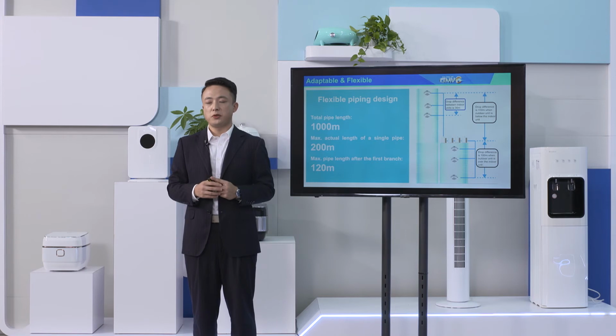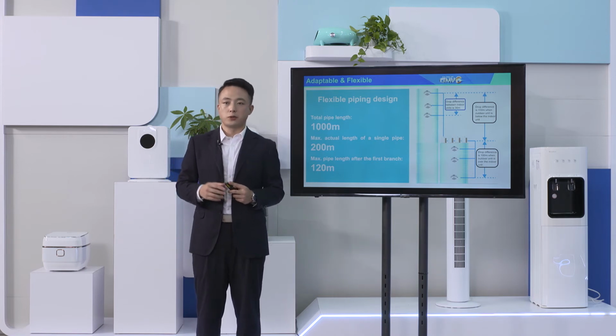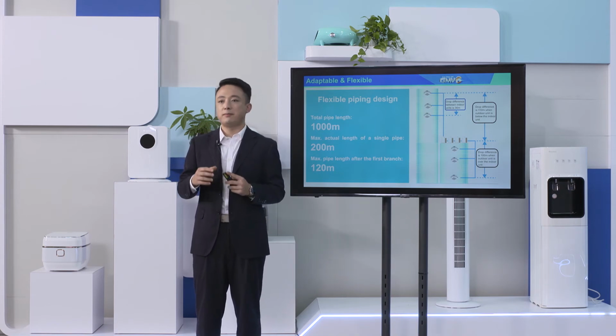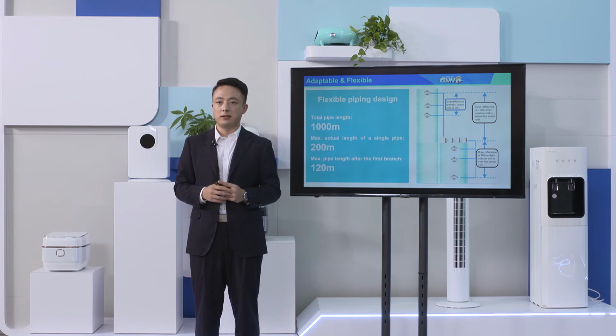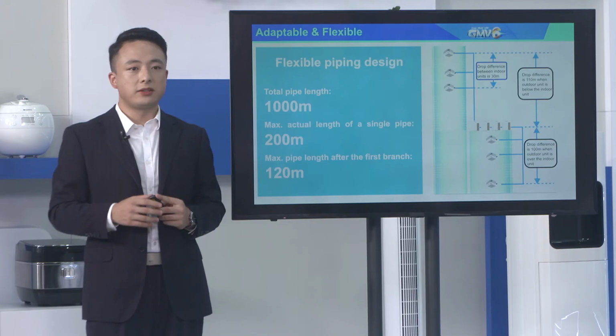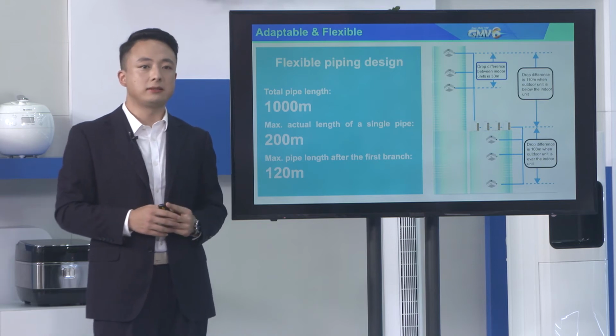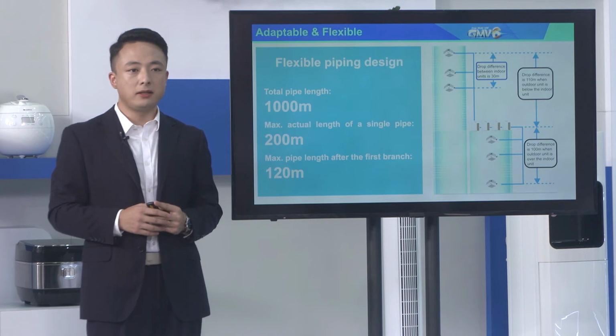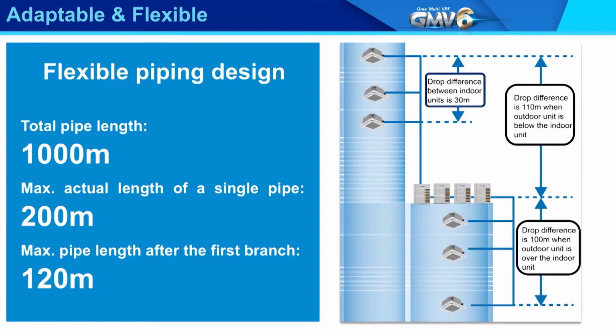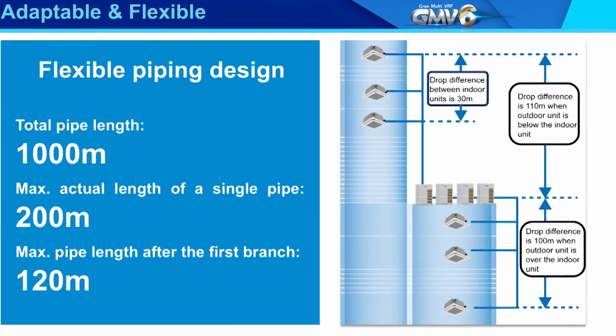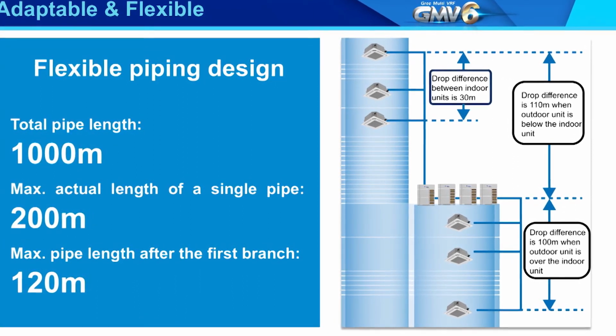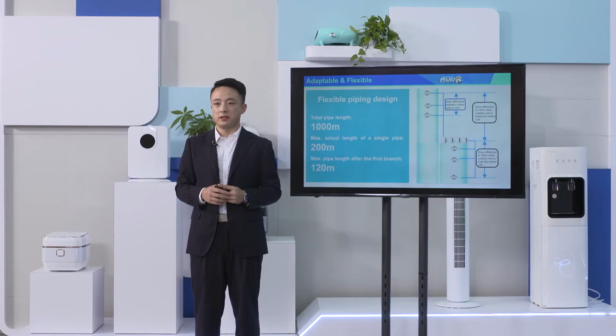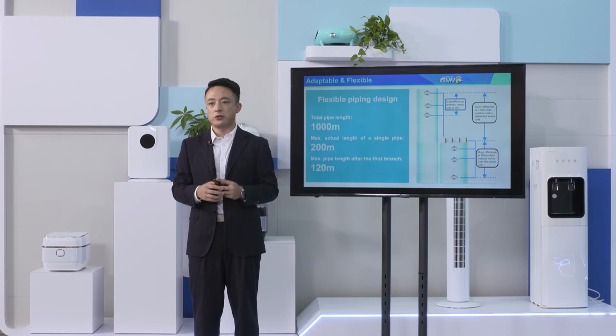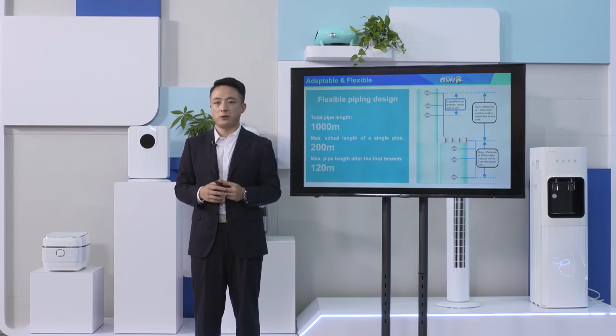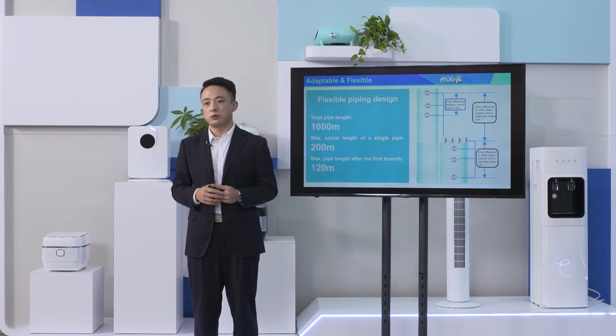Each unit adopts unique high drop pressure control technology to ensure the system has enough power to promote the circulation of refrigerant. And the maximum drop between indoor and outdoor units can reach 110 meters. The system also adopts flexible piping design and deep subcooling design, and it can be minus 35 degrees Celsius. We significantly reduce the pressure loss of long pipes. The total pipe length can reach 1,000 meters. The pipe length from the furthest indoor unit to the outdoor unit can reach 200 meters, and the length from the first branch pipe to the last one can be 120 meters.